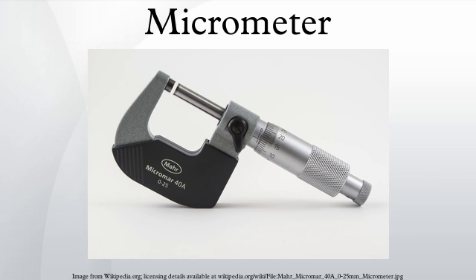If the micrometer is in good condition, then they are all so near to 0 that the instrument seems to read essentially right on all along its range. No noticeable error is seen at any locale. In contrast, on a worn-out micrometer, one can chase the error up and down the range, that is, move it up or down to any of various locales along the range, by adjusting the barrel, but one cannot eliminate it from all locales at once. Calibration can also include the condition of the tips, any ratchet, and linearity of the scale.